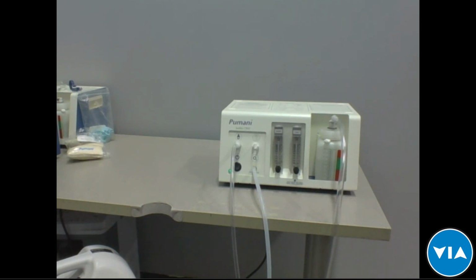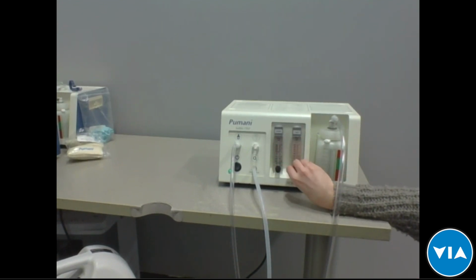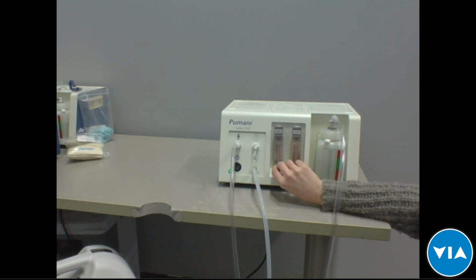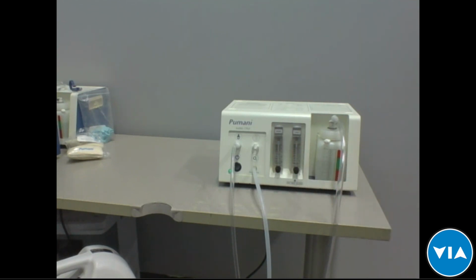And then you adjust the knob according to the settings in order to get a certain FiO2, so a percentage of oxygen that the baby's getting. The oxygen flow meter shows how much oxygen is going into the machine. The total flow meter shows how much room air, so 21% air, is going into the machine. You use the total flow meter to adjust the room air. When you're trying to adjust the oxygen, you should actually be using the flow meter on your concentrator or on your tank to do the adjustment.